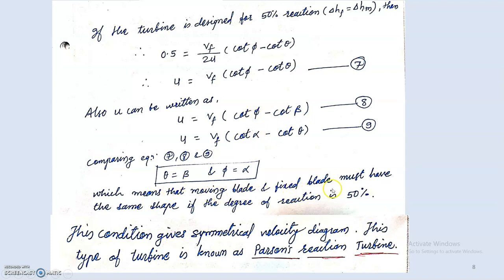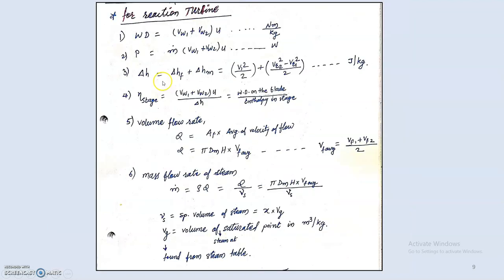The condition θ = β and φ = α means that the moving blades and fixed blades have the same shape when the degree of reaction is 50%. This gives a symmetrical velocity diagram, and this type of turbine is known as the Parsons reaction turbine — named after the scientist who developed it. Whenever a problem mentions a Parsons turbine, it is by default a 50% reaction turbine with θ = β and φ = α.